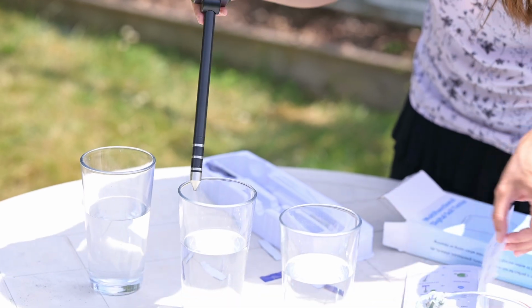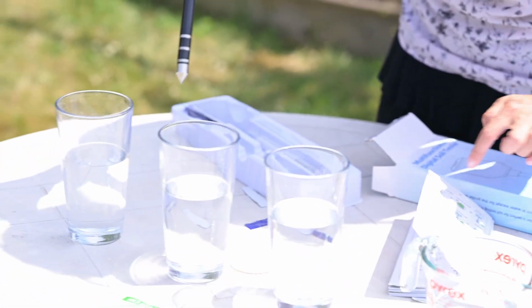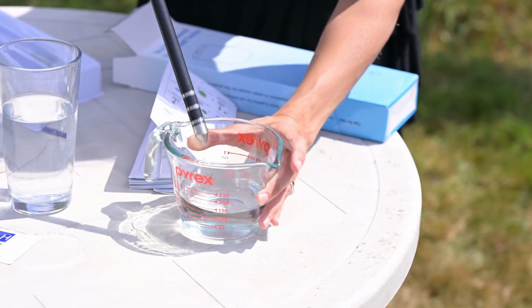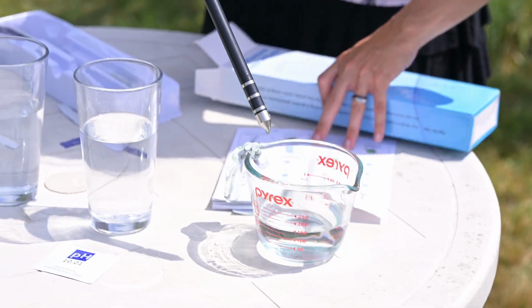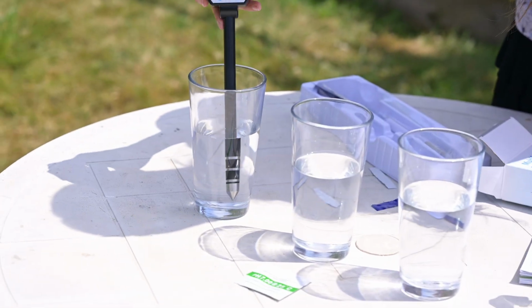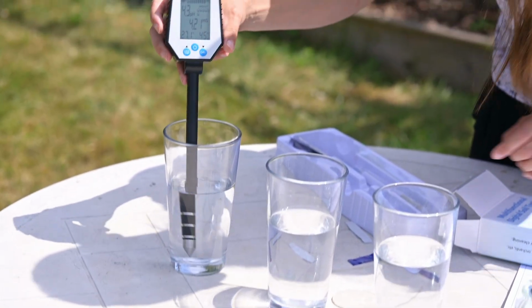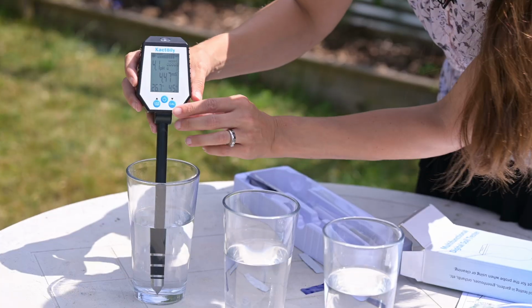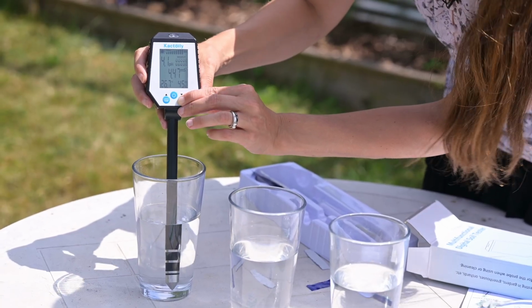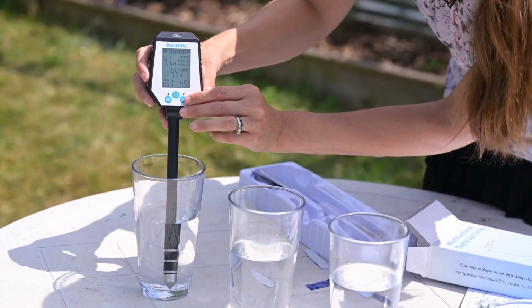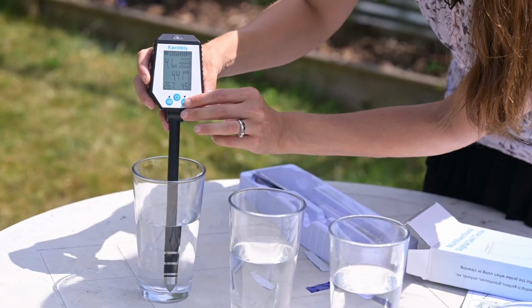Okay. And then clean the probe. It's showing it going in water to clean the probe. So we're gonna do that. Clean the probe. Now, we're gonna put it in the 4.0. Stir and wait for it to stabilize. 4.1, okay, close enough. We're going to press it, and the pH is gonna blink. 1, 1,000, 2, 1,000, 3, 1,000.